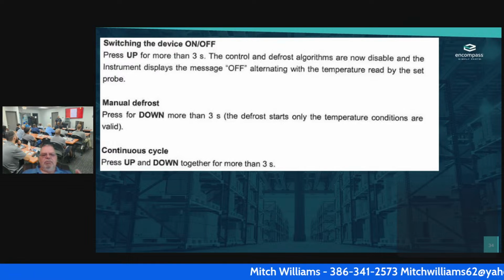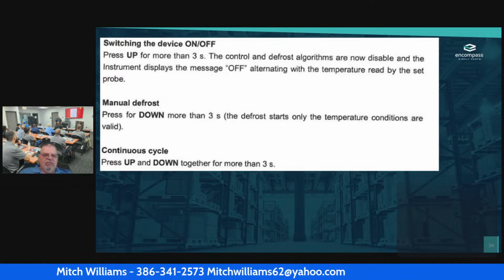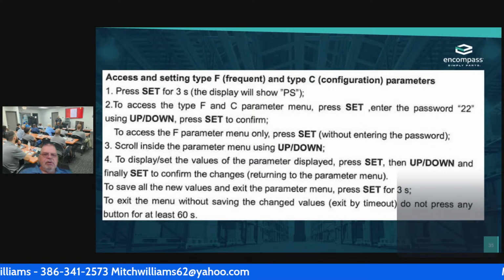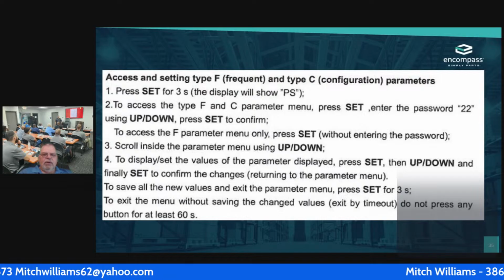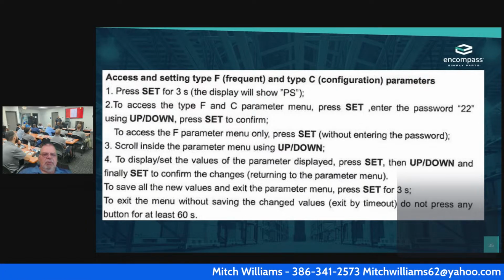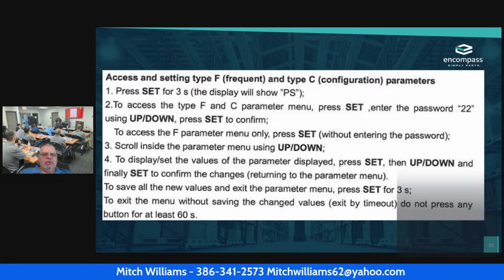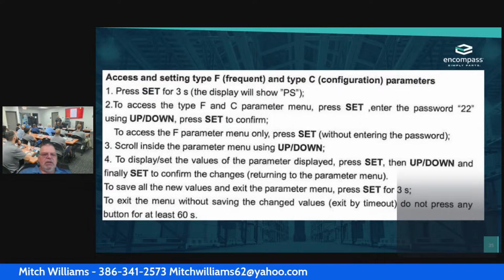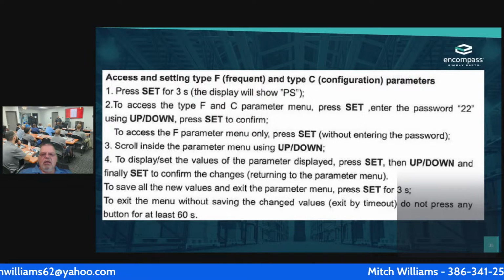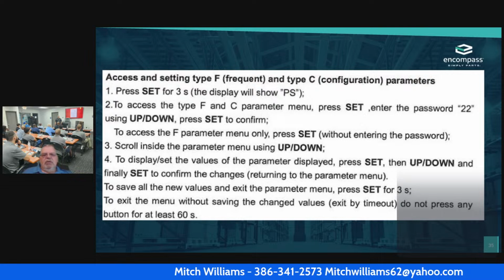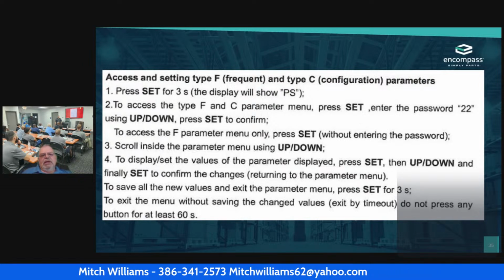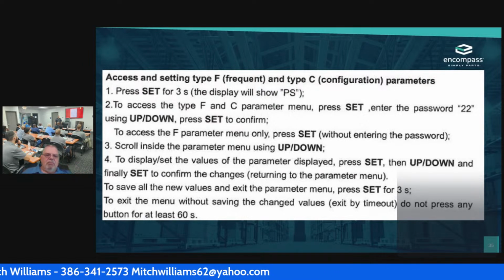Continuous cycle: press up and down together for more than 3 seconds. To access the frequent and the configuration parameters, once again, I'm going to press set for 3 seconds. The display will show PS. To access the F and C parameter menu, press set. Enter the password of 22 by using the up and down buttons. Once I'm done, I press the set button.